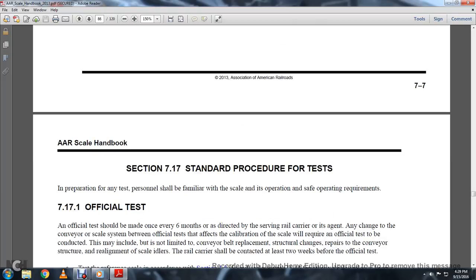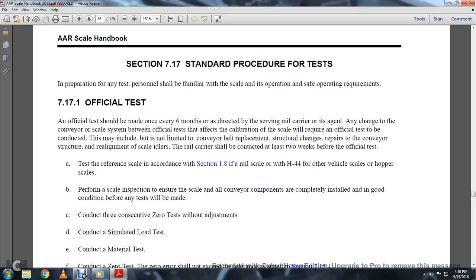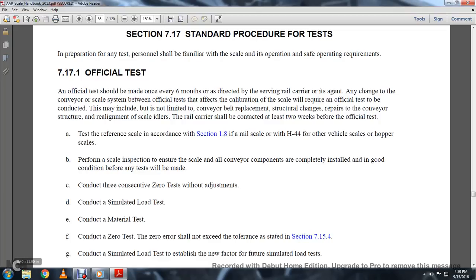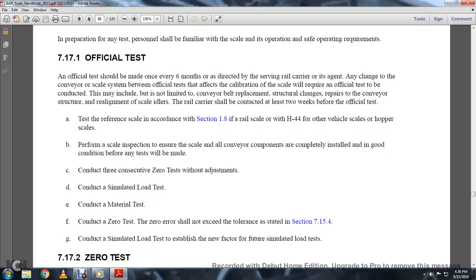Section 717, Standard Procedure for Testing. In preparation for any test, personnel should be similar or familiar with the scale and its operational state. Official tests should be made once every six months as directed by the servicing rail carrier or its agents. Any change of the conveyor scale system between official tests that affects calibration will require a new official test. This may include conveyor belt replacement, structural changes, or conveyor structural realignment. The idlers railway carriers should be conducted at least two weeks before the official test. Performance scale inspection shall ensure all conveyor components are completely installed and in good condition before the test is made.